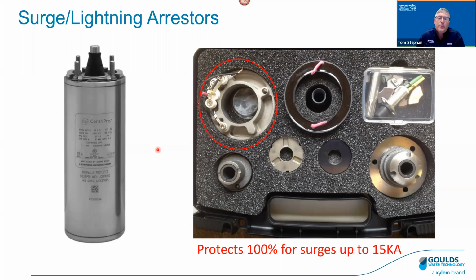So a lot of questions come up regarding surge arresters or lightning arresters. And so let's spend a couple minutes talking about that. If we look at a standard 4-inch submersible pump here on the left, and we look at some components here on the right, the first thing that we see here is the top end bell on the bottom side, which we don't normally see because these are not repairable. But if you were to take that top end bell off, you would see these surge arresters. Now it's a little tough to see in the picture, but there's one surge arrester for every leg. So in this case, we know that's a 3-wire motor because I have 3 surge arresters. If you have a 2-wire motor, then you're going to have 2 of these little guys. So this type of motor does have some built-in surge protection.